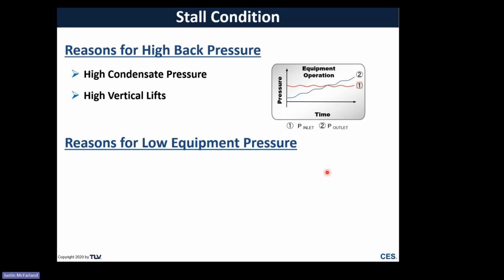There's things like high vertical lifts that might not be considered. So rule of thumb, for every 2 feet lift, you have 1 PSI increase in head pressure. And there's frictional losses. So whether that's due to corrosion that's degraded the surface of the pipe walls, or you have very, very small bore piping, or very old piping and things are just starting to degrade a little bit, frictional losses can certainly increase local back pressure.